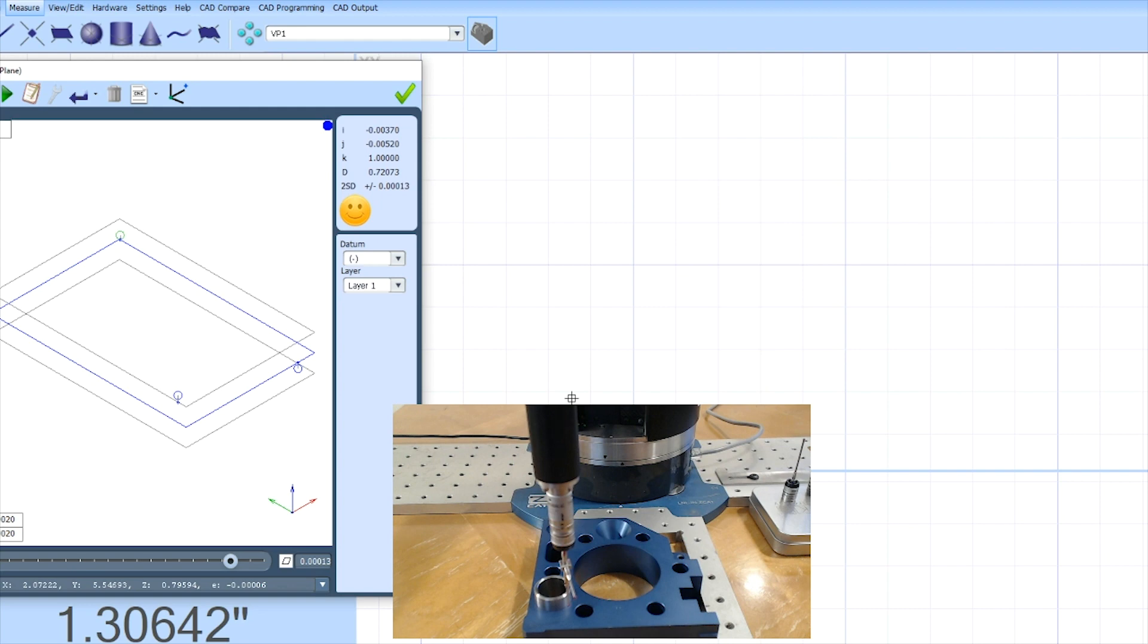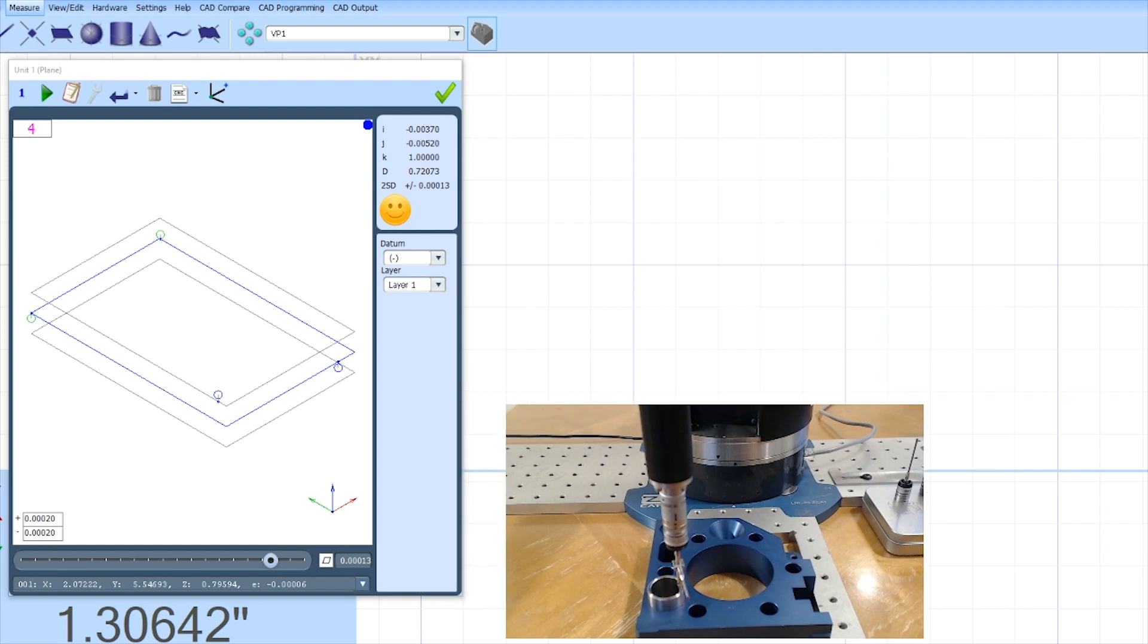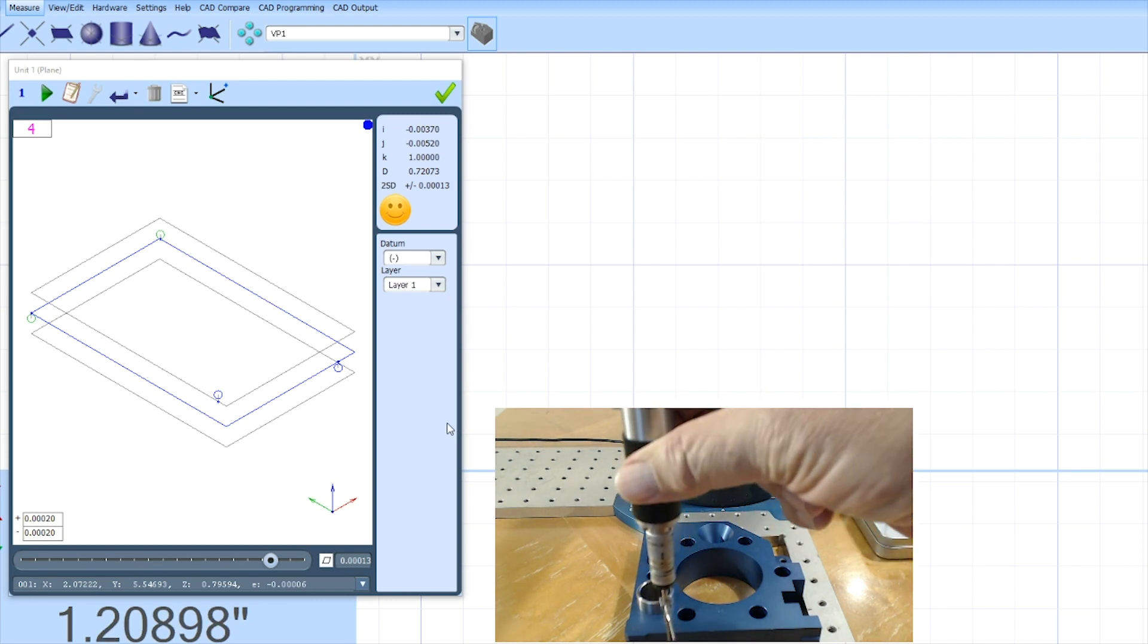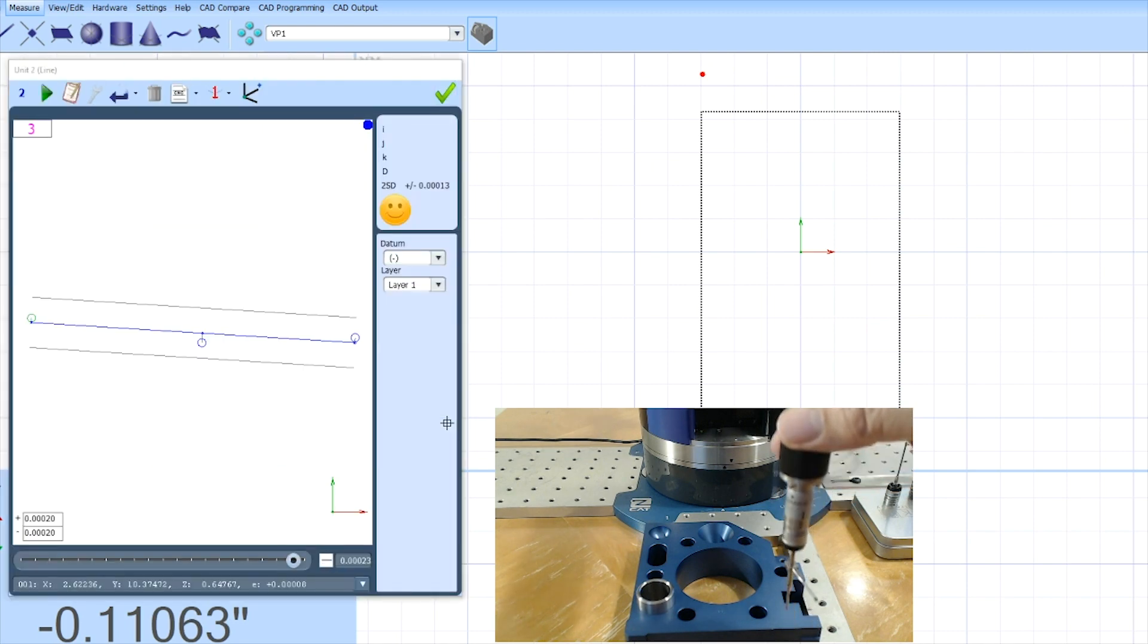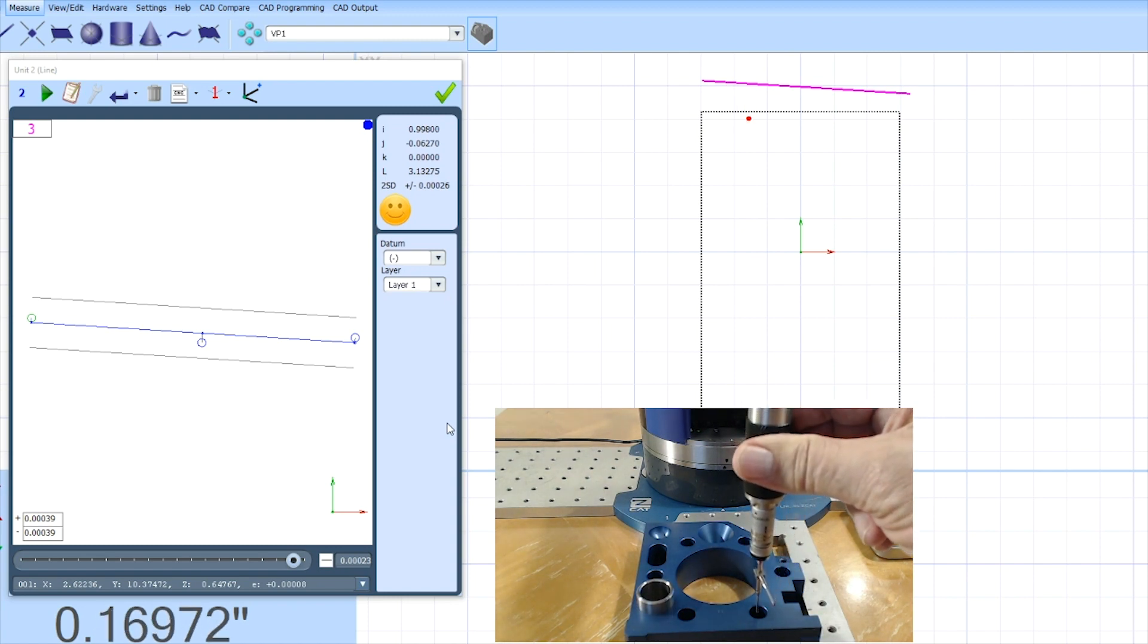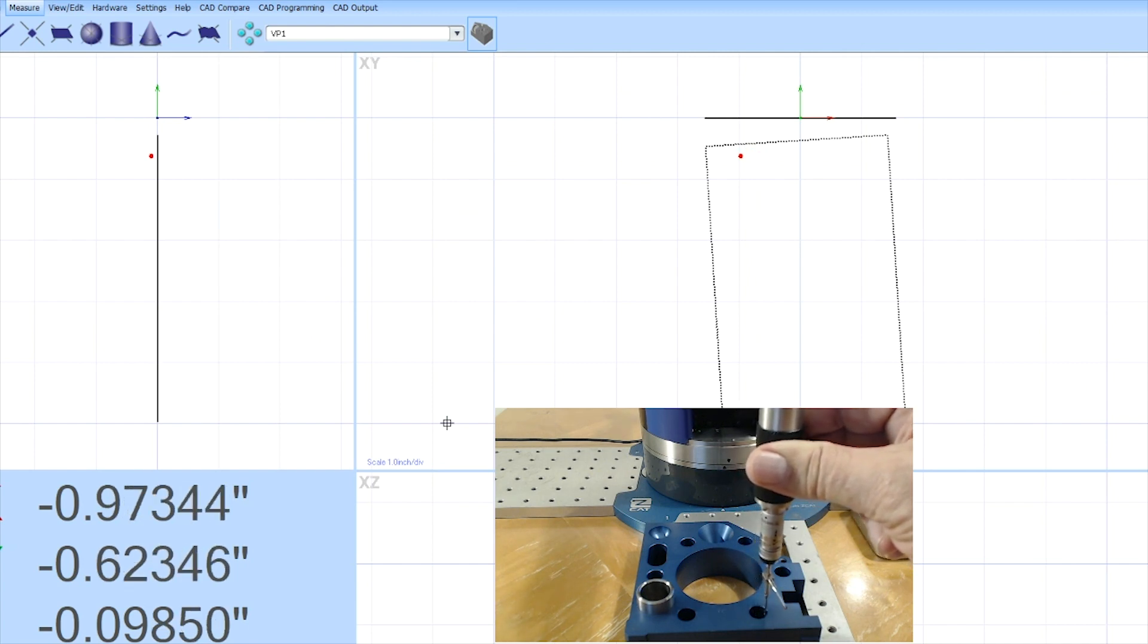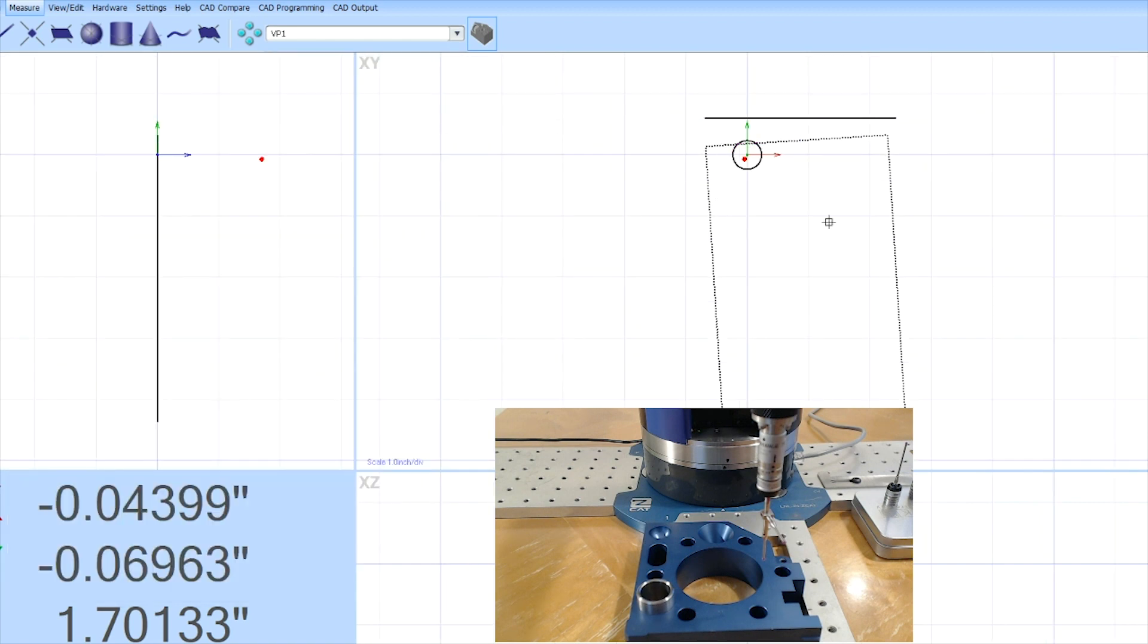I'm going to get this thing oriented so everybody can see it right. Move my camera a little bit and then I'm going to continue measuring. So maybe I measure a line on the front of this part. We're actually writing a program as we measure. You'll notice I measured a line and it predicted it was a line. I'm going to measure a diameter and it will predict that's a diameter. I'm going to tell it that that is a reference. Now you can see on my screen it's drawn a plane, a line, a diameter and made that a reference.